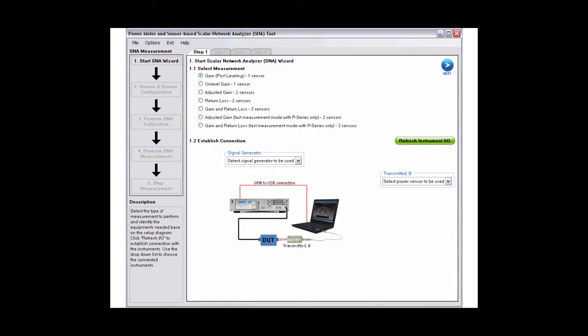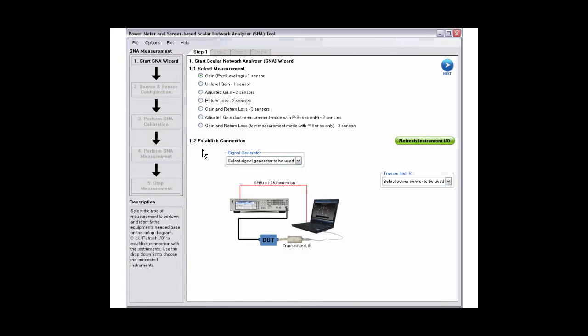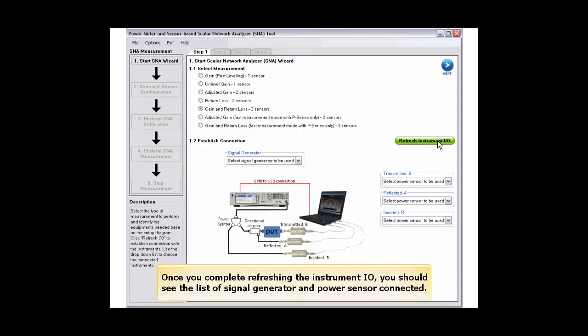Follow the procedures on the SNA measurement left panel to complete the gain and return loss measurement. Select gain and return loss measurement. Then, refresh the instrument I.O. to see the list of signal generator and power sensor connected to your PC.